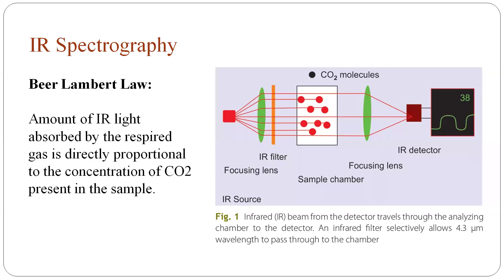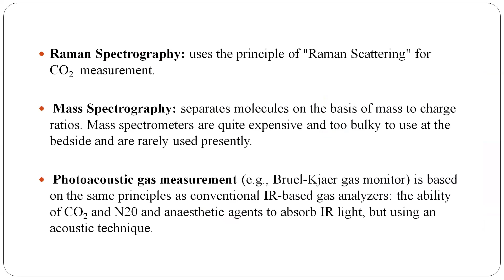Coming to Raman spectrography, it uses the principle of Raman scattering for carbon dioxide measurement. In mass spectrography, it separates molecules on the basis of mass to charge ratio. Mass spectrometers are quite expensive and too bulky to use at the bedside and are rarely used now. Photoacoustic measurement is based on the same principle as conventional infrared based gas analysis, that is, the ability of carbon dioxide, nitrous oxide and anesthetic agents to absorb infrared light, but using an acoustic technique.